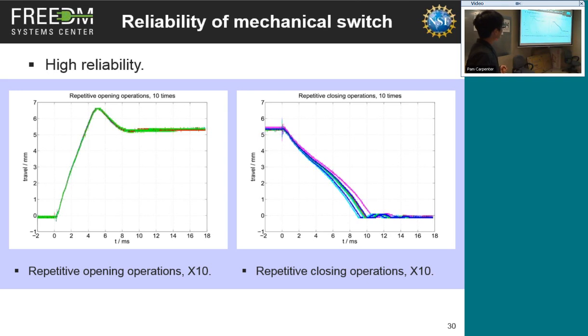For the 10 times opening operation, it occurs to me that they are also only one curve, so I think the opening is very good. But look at the closing - it's not as good as the opening, and one reason is that the speed is somehow slower. We did that on purpose; we wanted the closing to be slower.